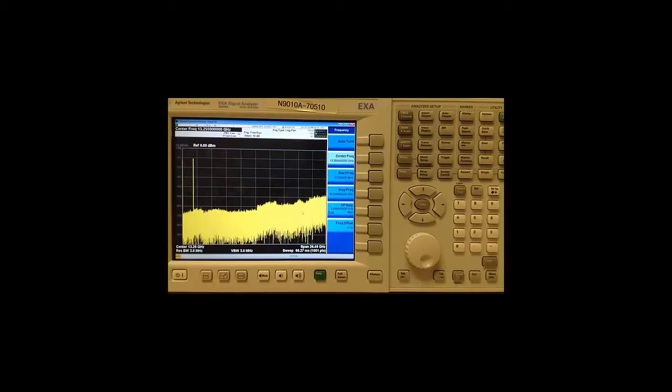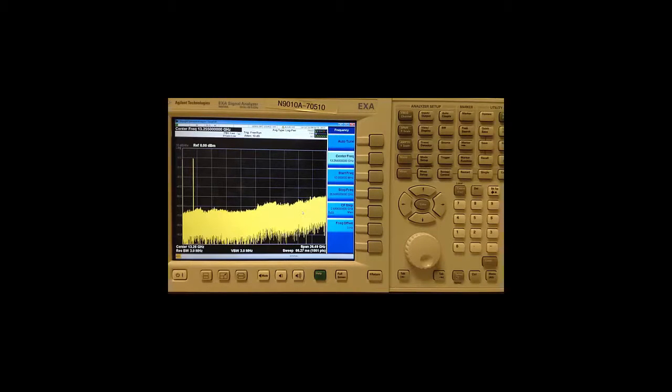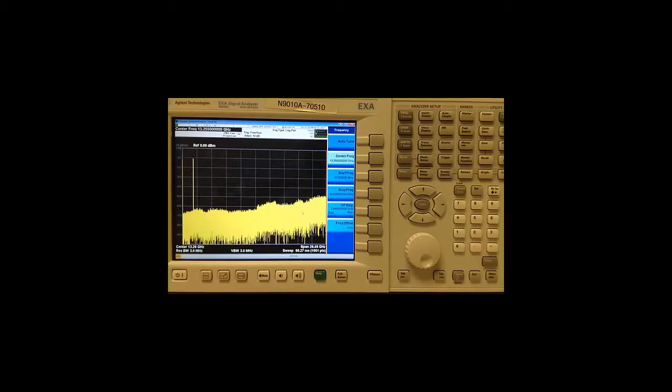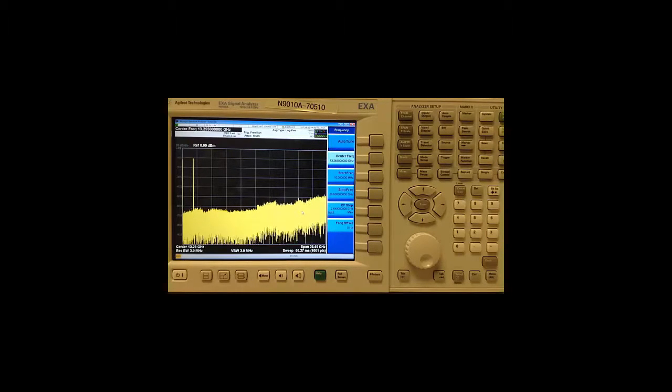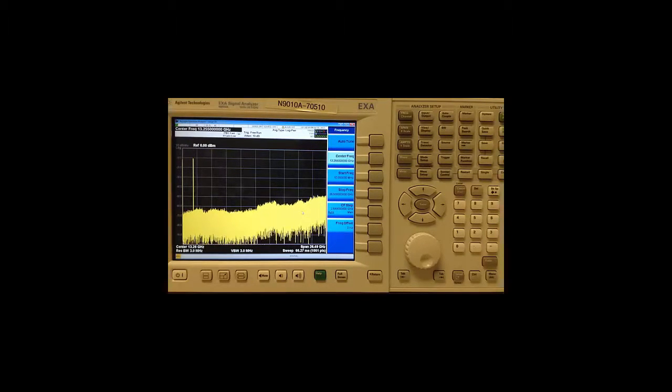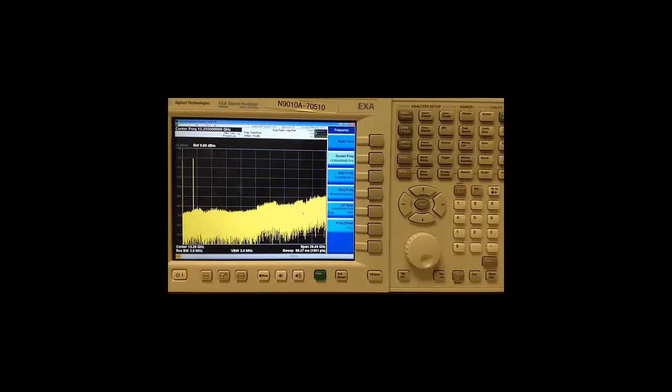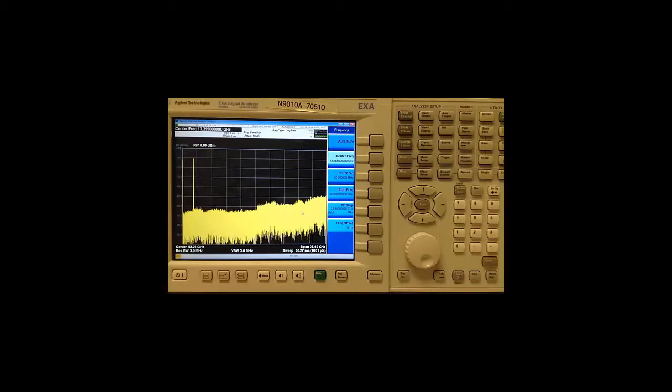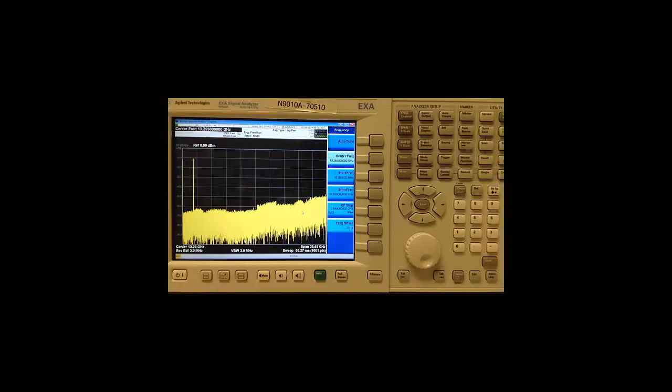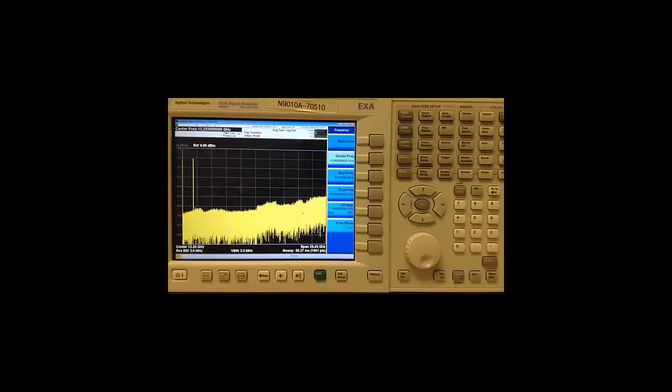Spectrum analyzers can be used to measure phase noise by way of the direct spectrum technique, which means we simply and directly tune to the input signal and measure its power spectral density at various offset frequencies. This is the oldest technique in the book and works well when the intrinsic phase noise of the analyzer is better than that of the device under test at the offset frequency of interest.